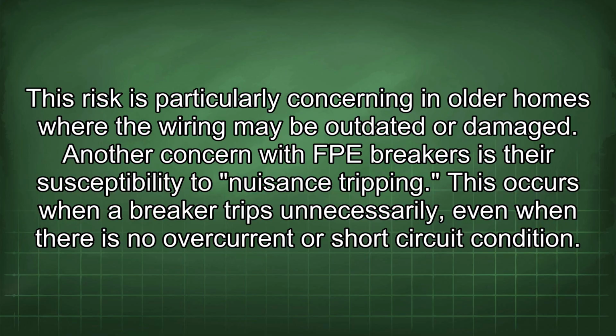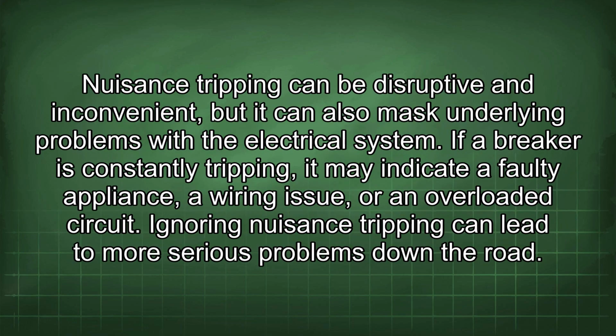Another concern with FPE breakers is their susceptibility to nuisance tripping. This occurs when a breaker trips unnecessarily, even when there is no overcurrent or short-circuit condition. Nuisance tripping can be disruptive and inconvenient, but it can also mask underlying problems with the electrical system. If a breaker is constantly tripping, it may indicate a faulty appliance, a wiring issue, or an overloaded circuit. Ignoring nuisance tripping can lead to more serious problems down the road.